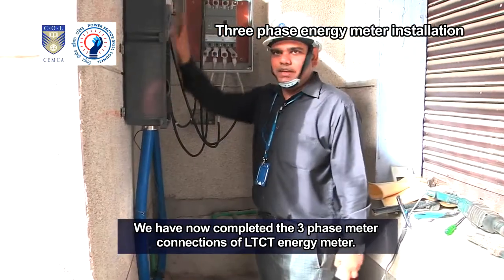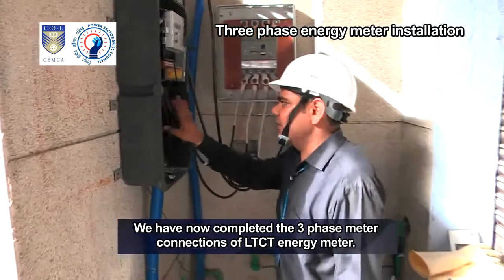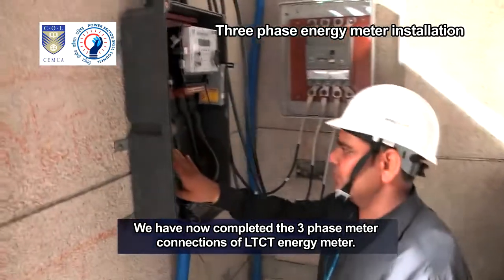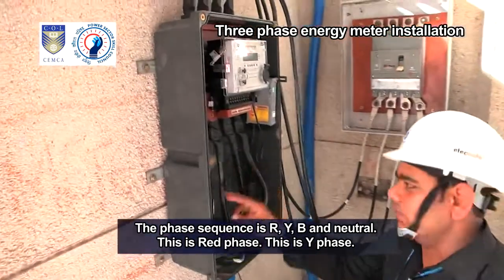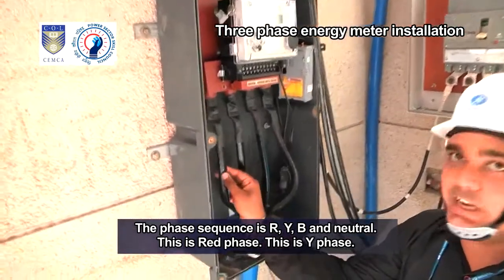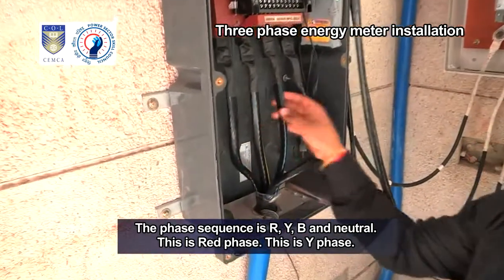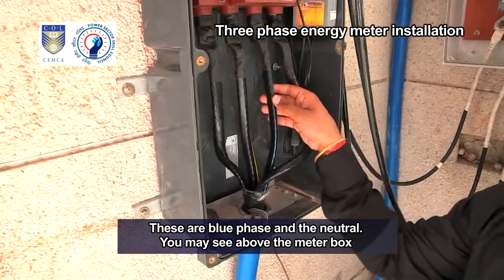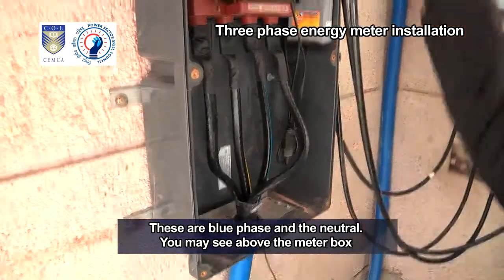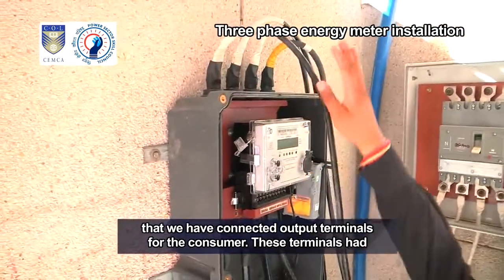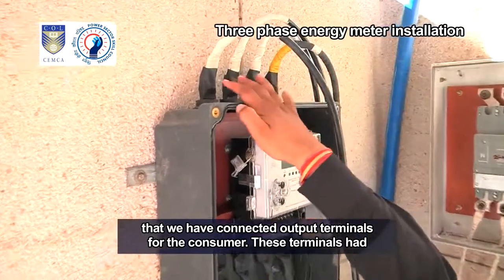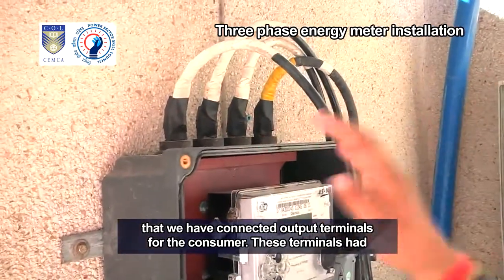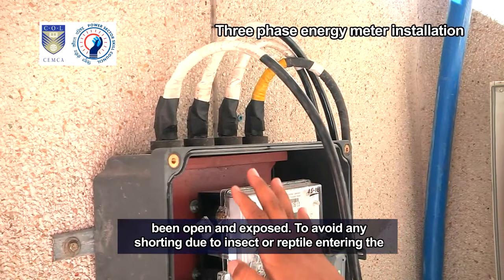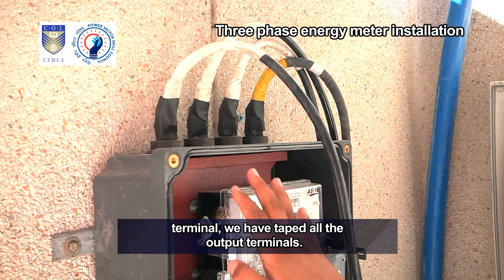We have now completed the 3-phase meter connections of LTCT energy meter. The phase sequence is RYB and neutral. This is red phase. This is Y phase. These are blue phase and the neutral. You may see above the meter box that we have connected output terminals for the consumer. These terminals had been open and exposed. To avoid any shorting due to insect or reptile entering the terminal, we have taped all the output terminals.